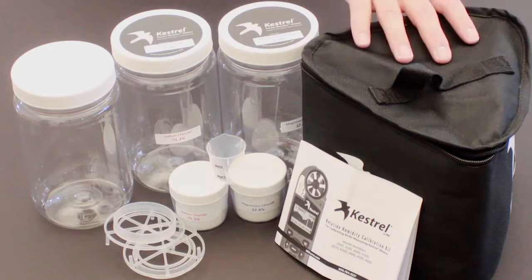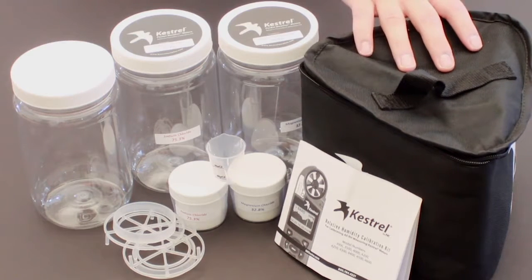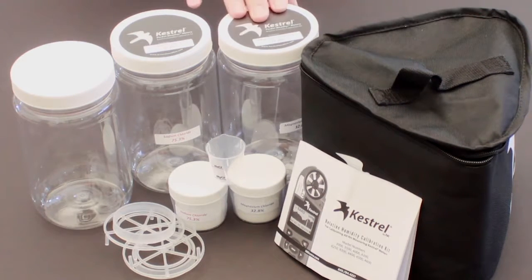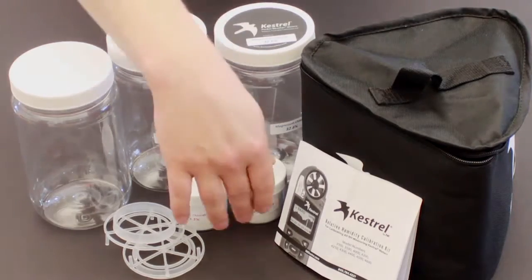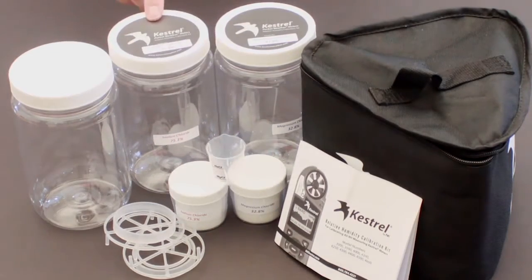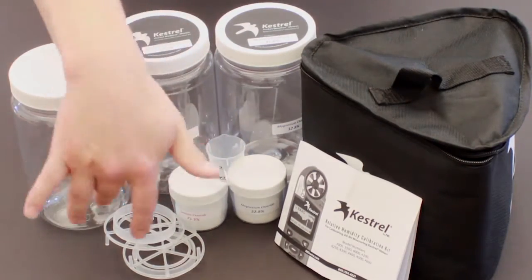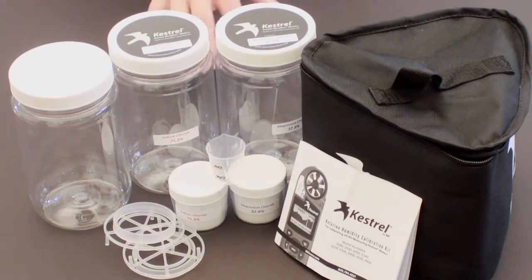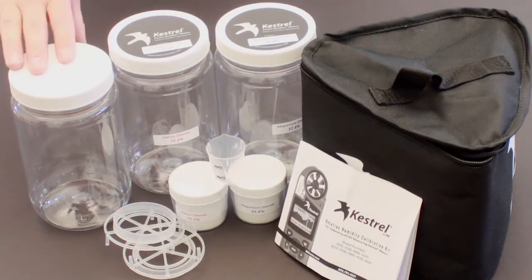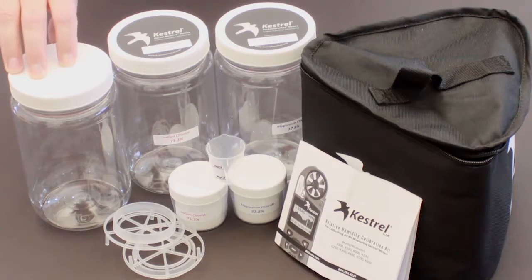We can get a Kestrel RH calibration kit, and customers can recalibrate their Kestrels in the field. The RH calibration kit comes with an insulated bag. The contents of this bag are magnesium chloride jar and salts, a sodium chloride jar and salts. Both come with grids that you will put in a jar, and then one jar that will be filled with tap water to stabilize the temperature.